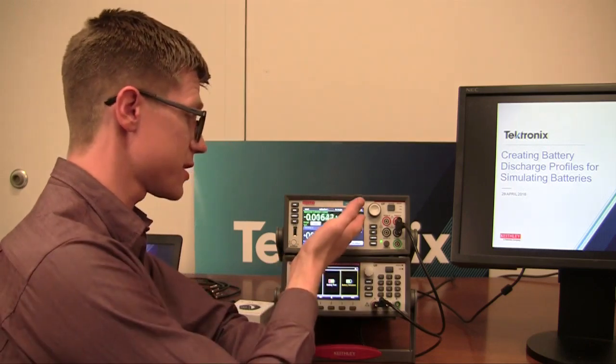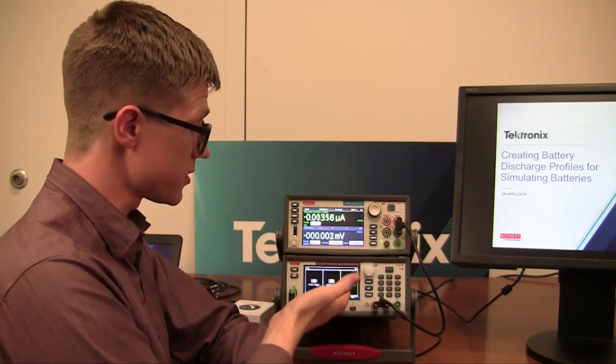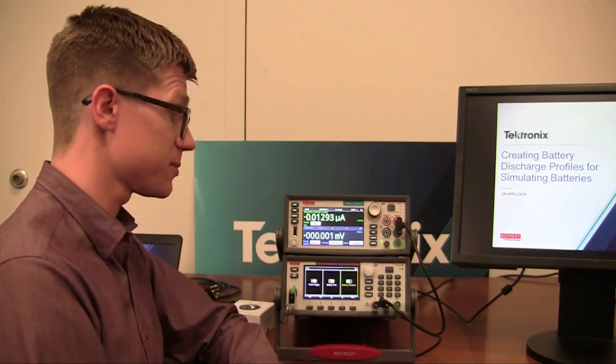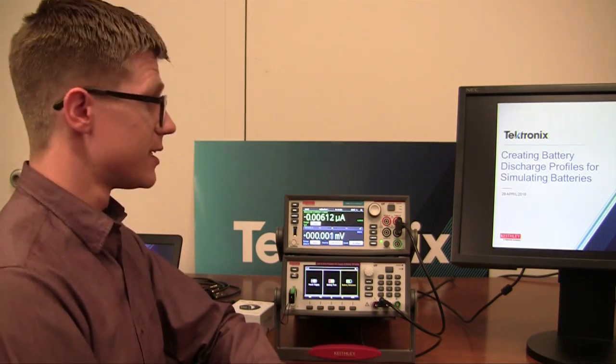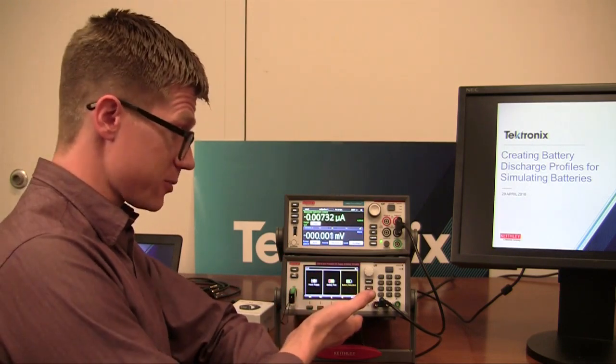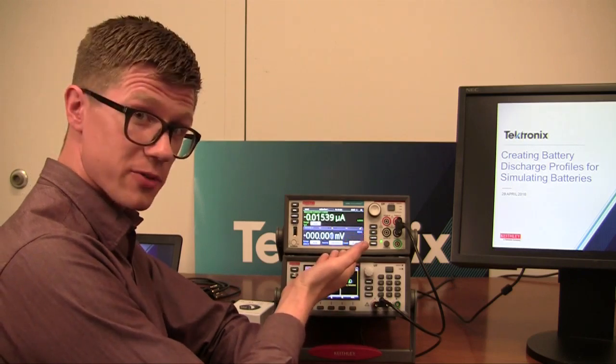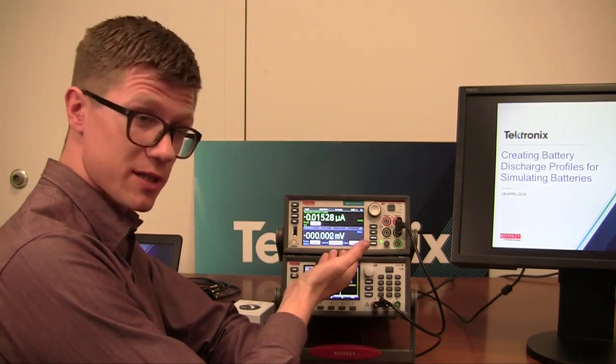So essentially what we're going to do is connect the 2460, in this case, to the 2281S Precision DC Supply and Battery Simulator and we're going to simulate a battery with this one and then discharge the battery with this and create a model of it.